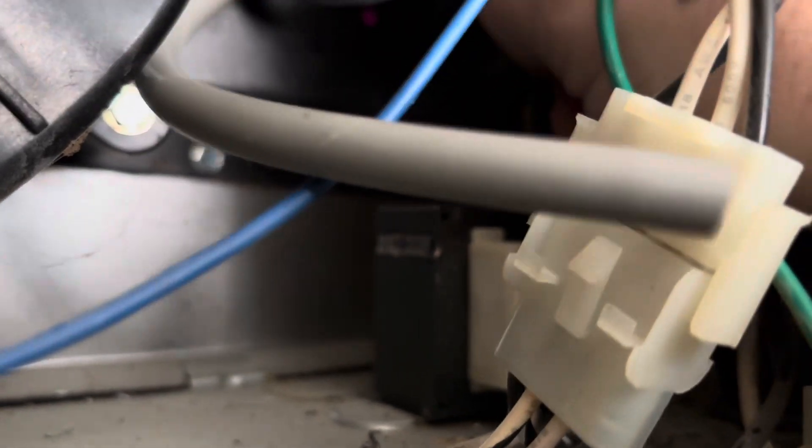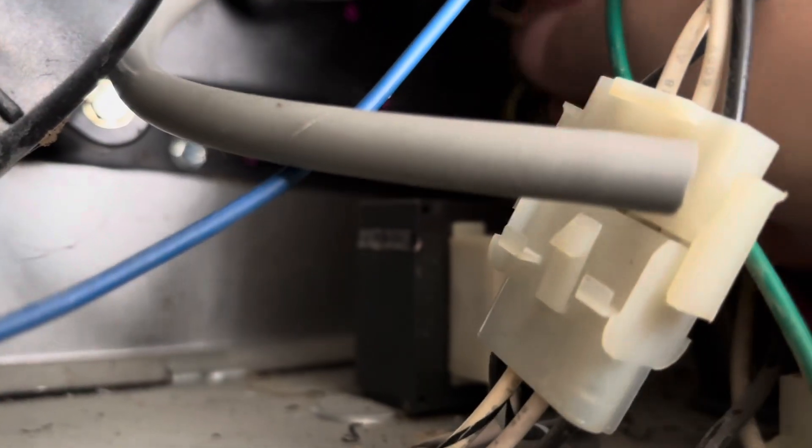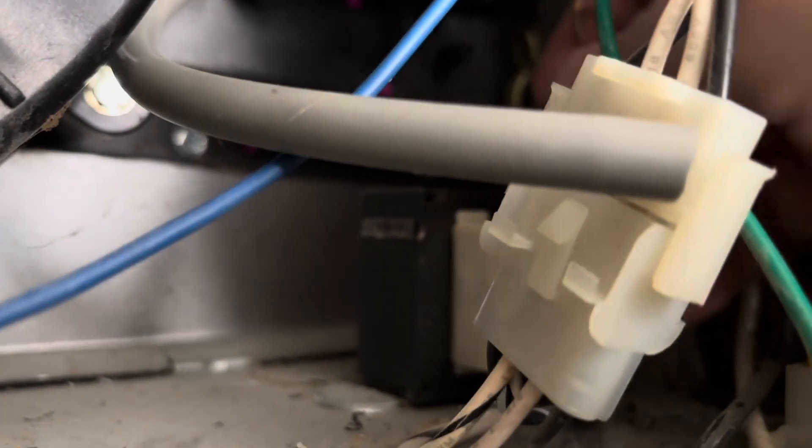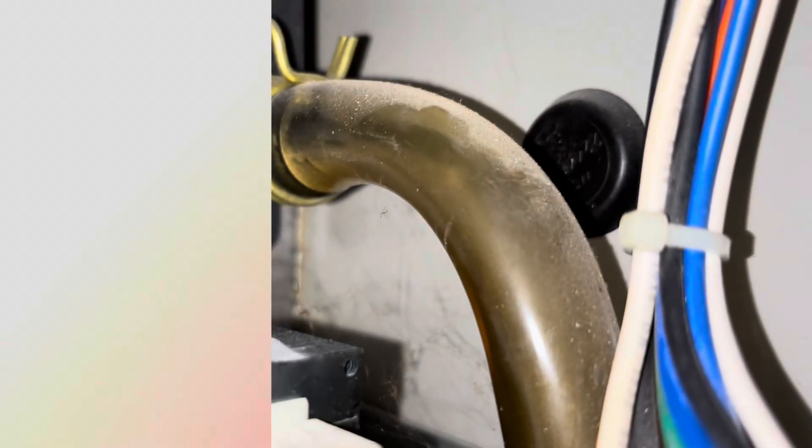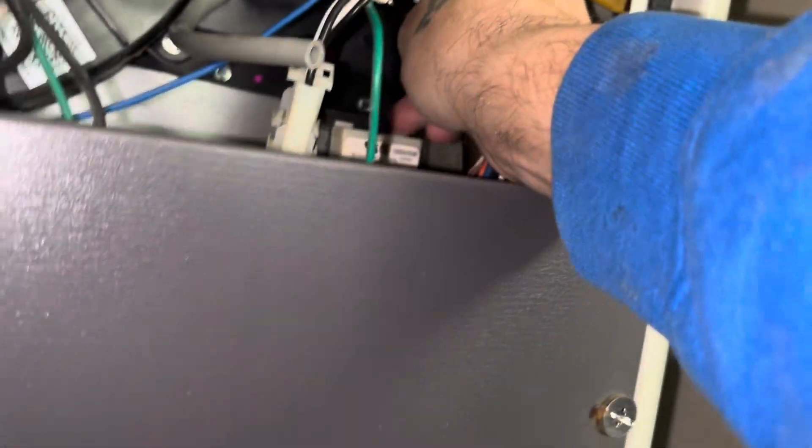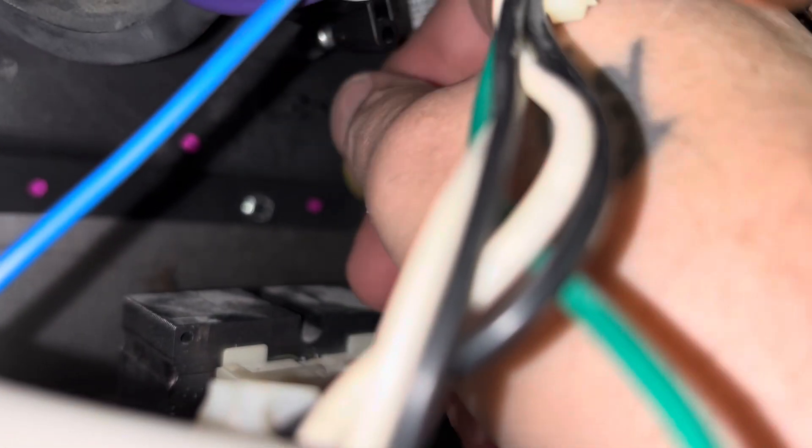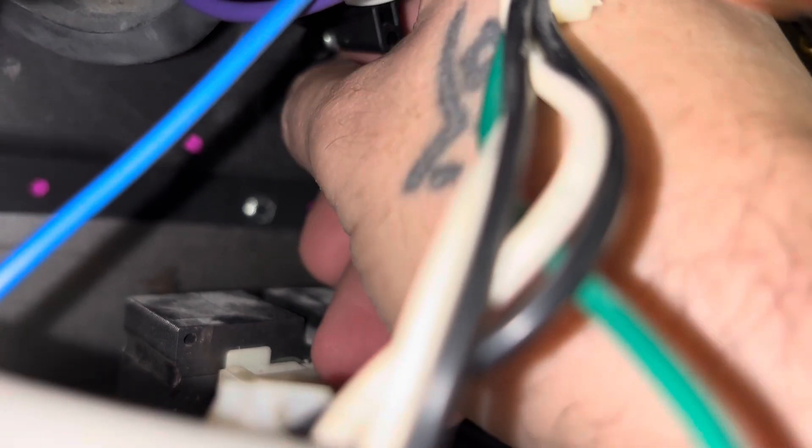It was just clogged. So I'm taking a little tiny drill bit here, and where the tubing for the pressure switch connects at, to that little black plug right there, that was clogged. And I'm just taking a drill bit and clearing that out to make sure it's good and clear. And we're good. So you can see, I just got it in there. I'm just going to work it back and forth, make sure it's good there.